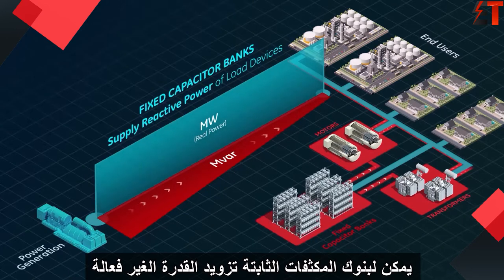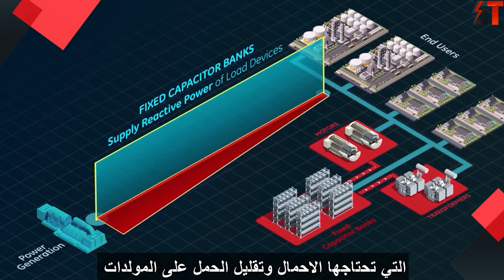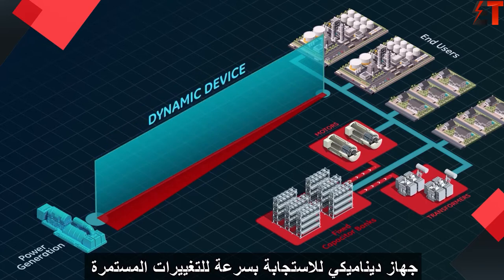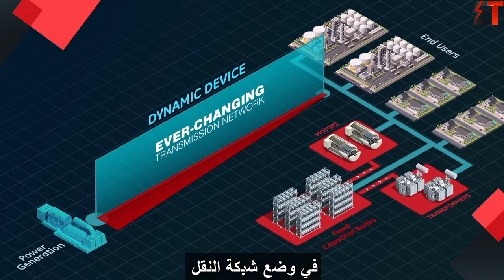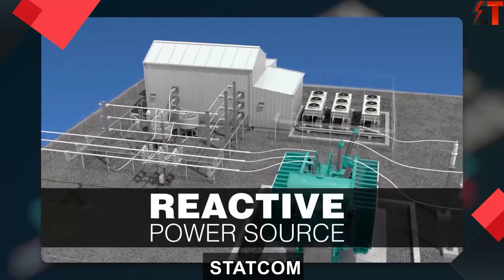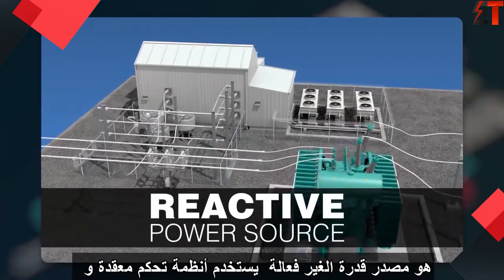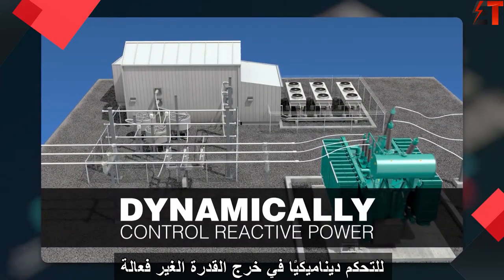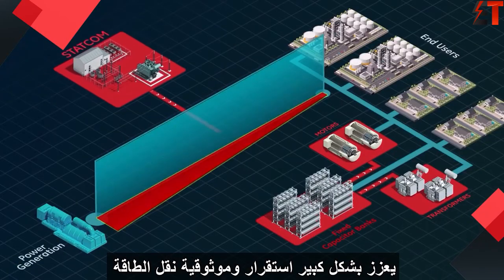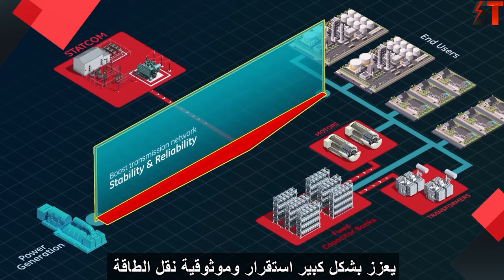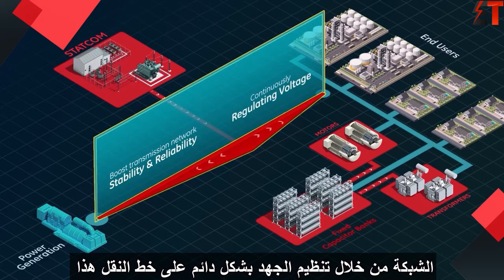Fixed capacitor banks can supply the reactive power needs of the load devices and reduce the load on the generators. However, a dynamic device is needed to rapidly respond to the ever-changing conditions of the transmission network. A static synchronous compensator, or STATCOM, is a reactive power source that uses complex control systems and IGBT switches to dynamically control reactive power output. STATCOMs can significantly boost the stability and reliability of the power transmission network by continuously regulating the voltage on the transmission line.